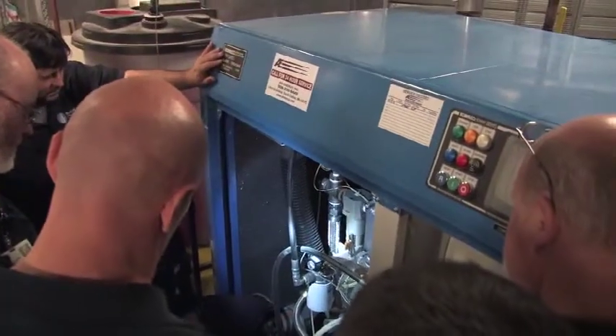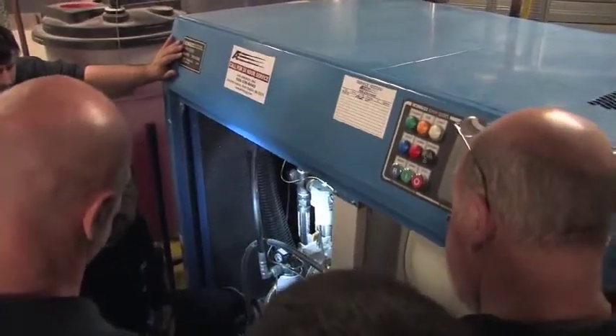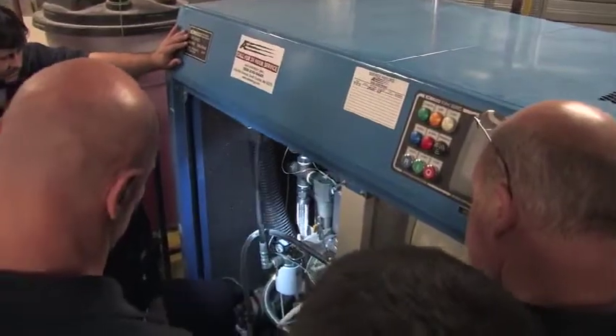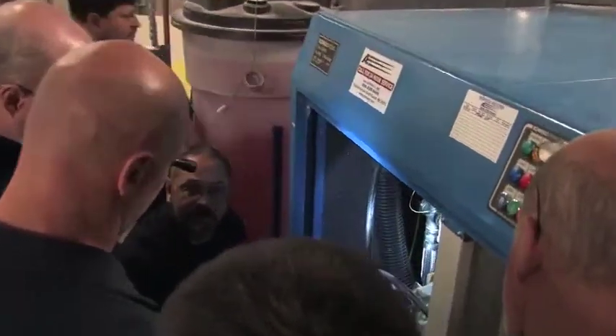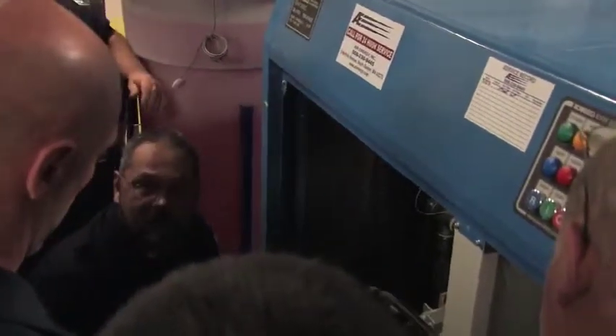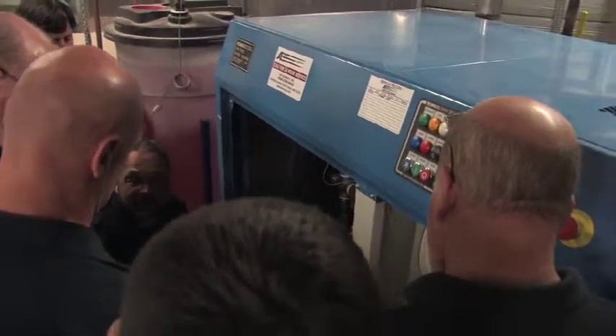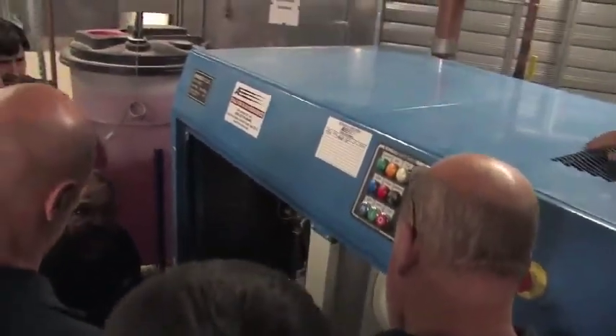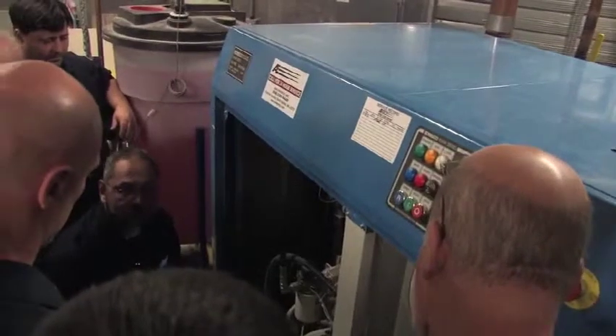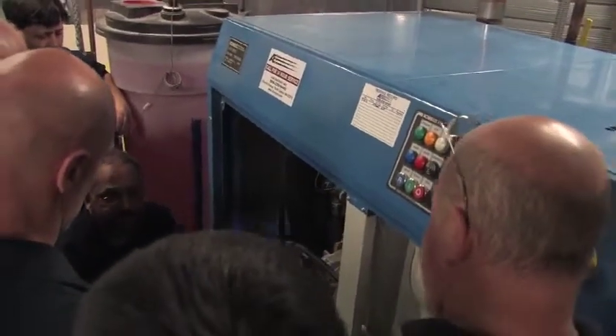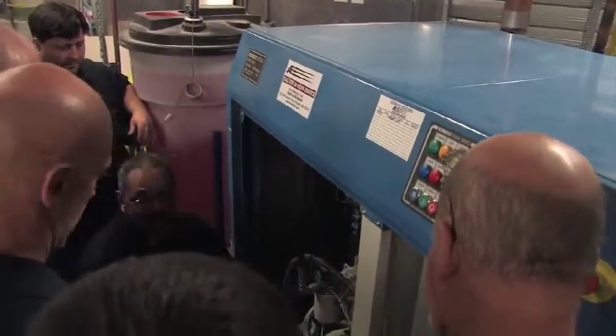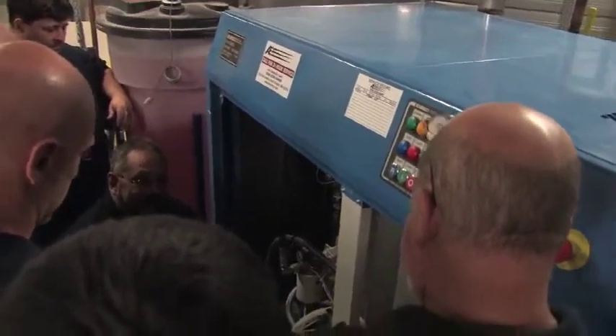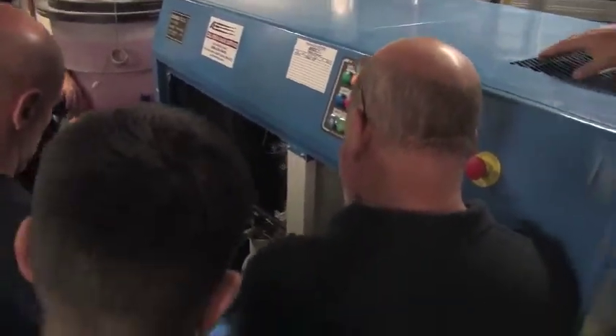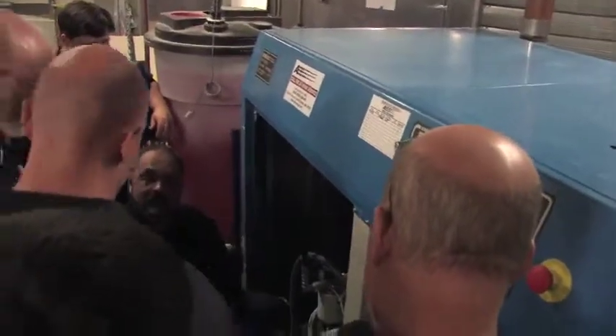These screws are coated with a proprietary Teflon-style coating, and when it explodes and blows into steam, it erodes the Teflon coating off and you degrade the performance, and you also tend to make the machine run hotter over time. Actually, that's pretty much how air ends eventually wear out and need to be replaced: the coating eventually wears off after 50,000 hours or whatever. Yeah, you've got some machines that have been here a long time now. But the one thing that will accelerate that damage is hitting them directly with moisture.